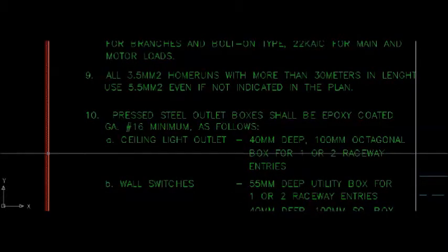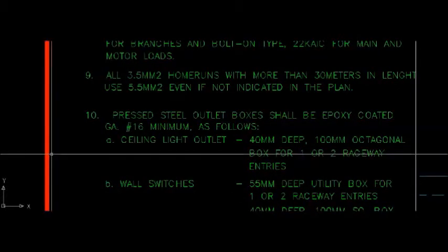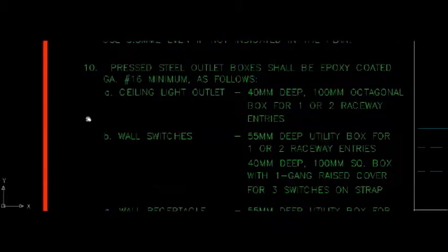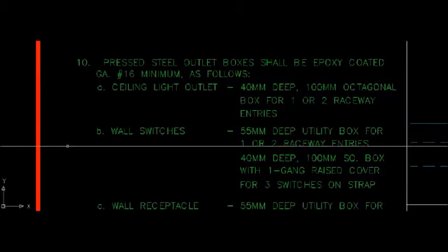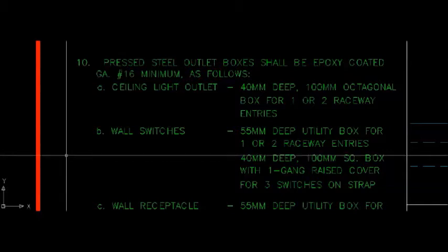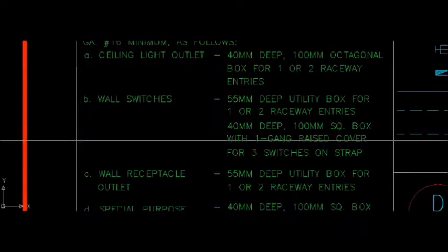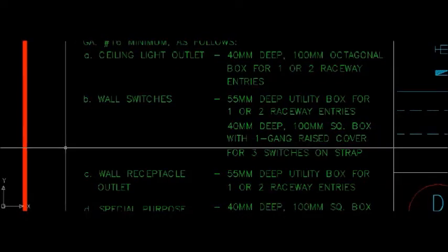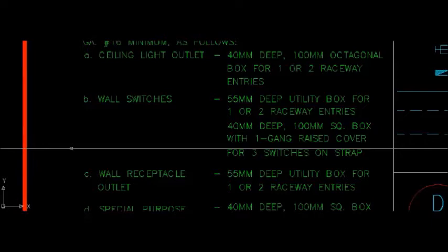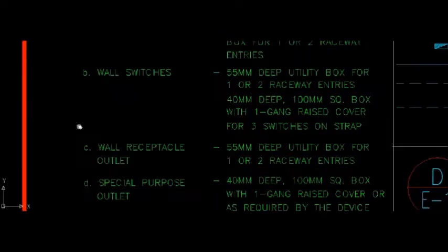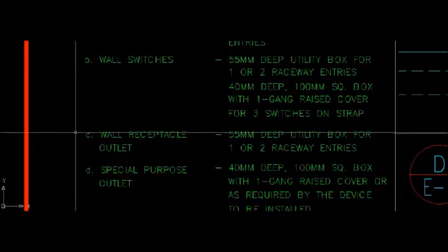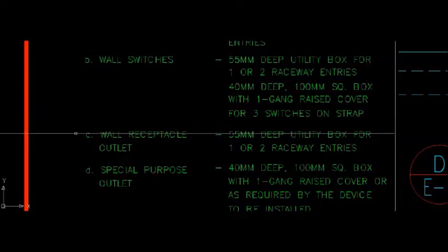All 3.5 mm squared home runs with more than 30 meters in length use 5.5 mm squared even if not indicated in the plan. Pressed steel outlet boxes shall be epoxy coated, GA number 16 minimum, as follows. Ceiling light outlet, 40 mm deep, 100 mm octagonal box for 1 or 2 raceway entries. Wall switches, 55 mm deep utility box for 1 or 2 raceway entries.